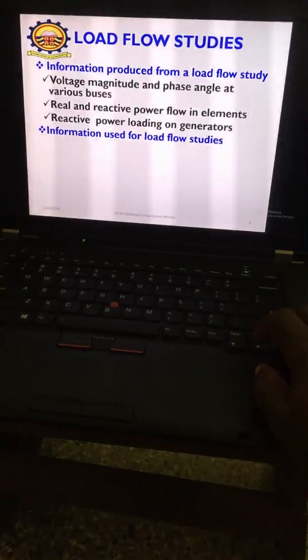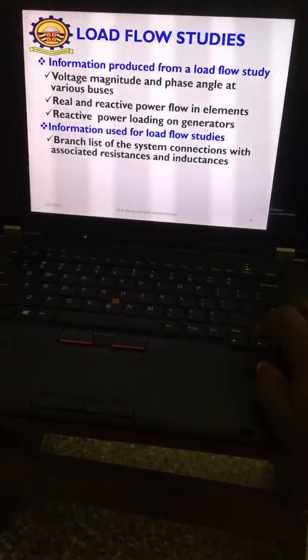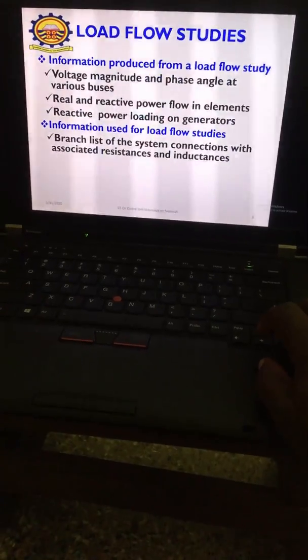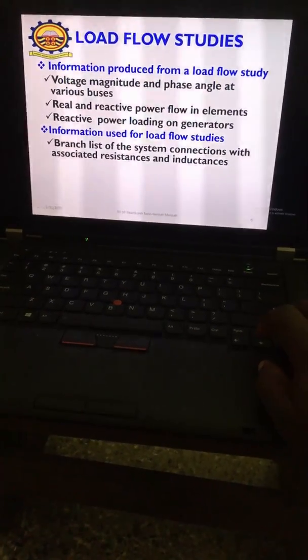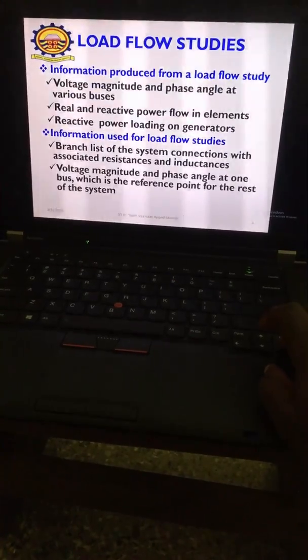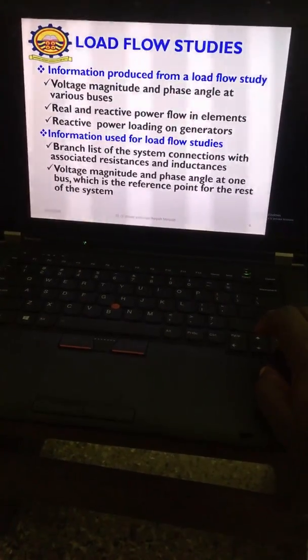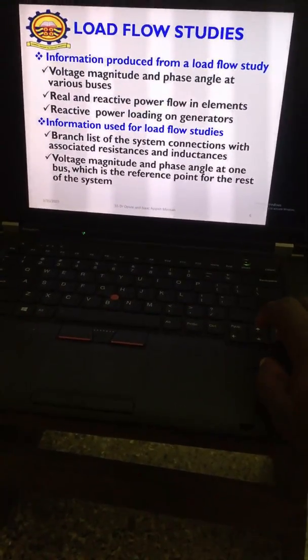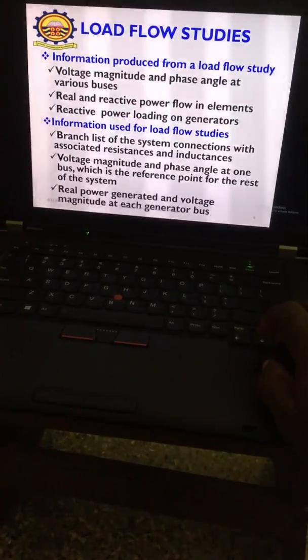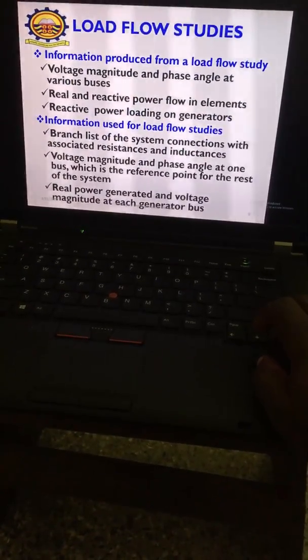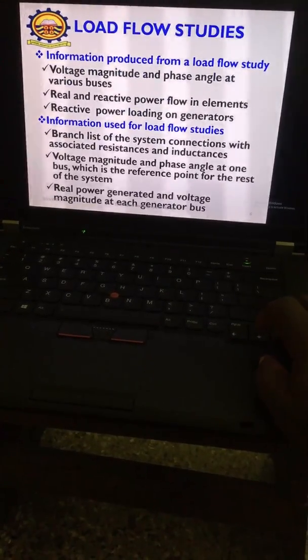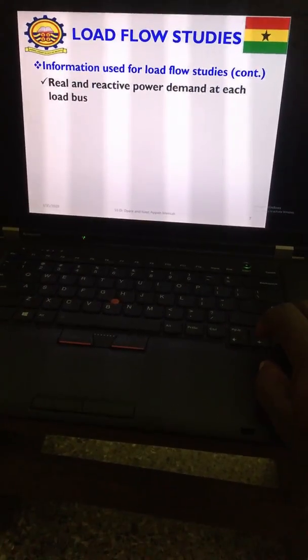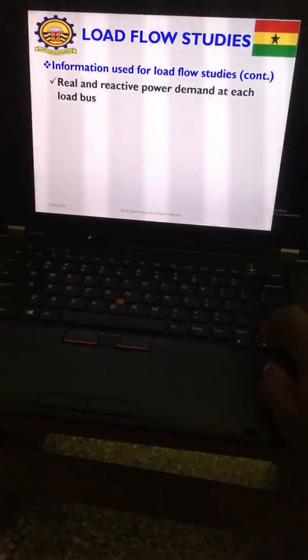Information used for load flow studies will be the branch list of system connections with associated resistances and inductances, voltage magnitude and phase angles at one bus which is the reference point, the real power generated and voltage magnitude at each generator bus, and the real and reactive power demand at each load bus.